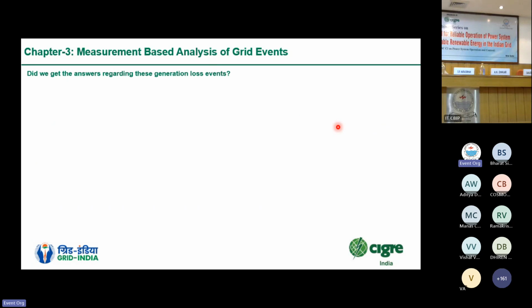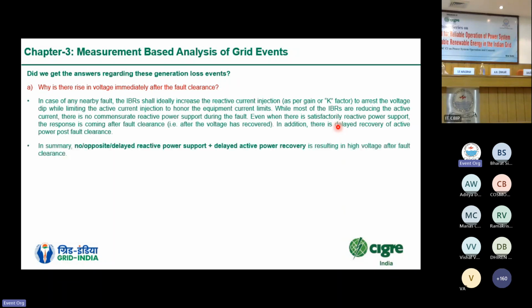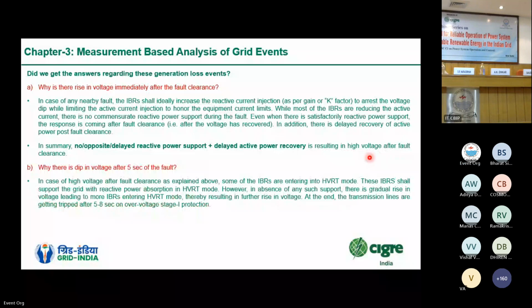So did we get the answers that we were expecting after this analysis based on the PMU data? Why is there a rise in voltage immediately after the fault clearance? The answer is no or opposite or delayed reactive power support from the plants, coupled with delayed active power recovery. This mainly results in high voltage immediately after fault clearance. The reason for the dip in voltage after 5 seconds is the tripping of many EHV lines on over voltage stage 1 setting after 5 to 6 seconds.